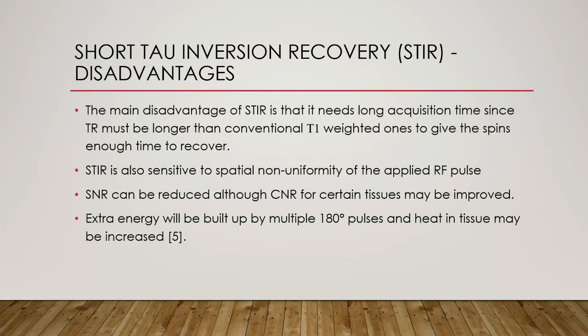The main disadvantage of STIR is that it needs a long acquisition time, since TR must be longer than in conventional T1-weighted sequences to give the spins enough time to recover. Fast spin echo is used as a solution to reduce this time to a reasonable amount. Also, STIR is sensitive to spatial non-uniformity of the applied RF pulse — if the strength of the RF pulse changes with position, then the tip angle of the inversion pulse also changes, causing a change in the quality of fat separation. Additionally, SNR can be reduced, although CNR for certain tissues may be improved, and extra energy built up by multiple 180 degree pulses may increase heat in tissue.